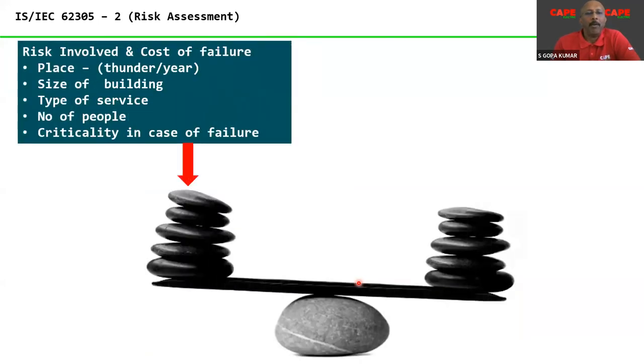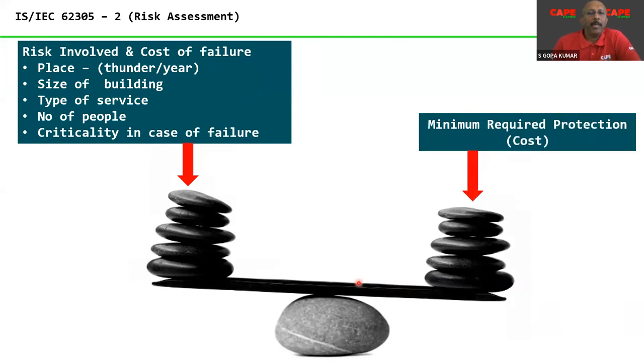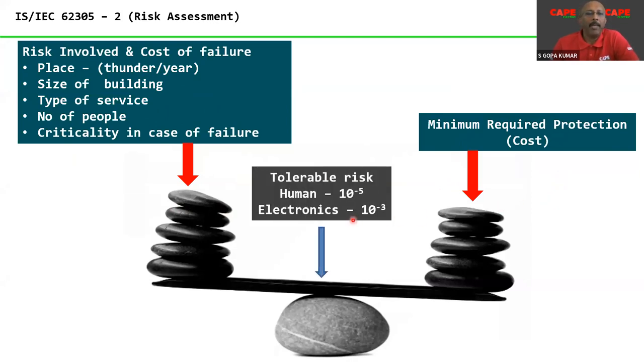Risk assessment, the second part of lightning protection, the IS/IEC 62305 part 2, risk assessment. Risk assessment is a technique with which the risk involved in a building is calculated. For example, depending upon the place where your building is located, number of thunderstorm days per year, size of building, type of service, number of people, and criticality in case of failure at one site. And then the standard gives you a kind of tolerable level. Tolerable level means up to what level you can have safety.